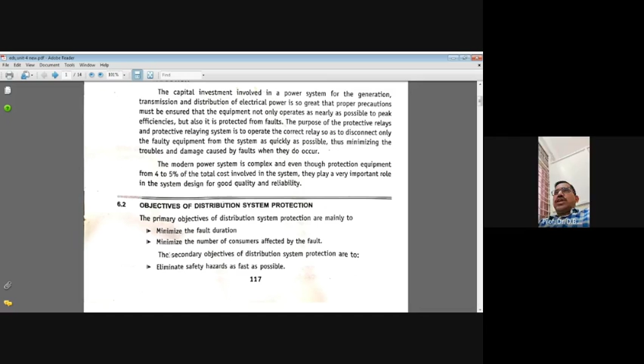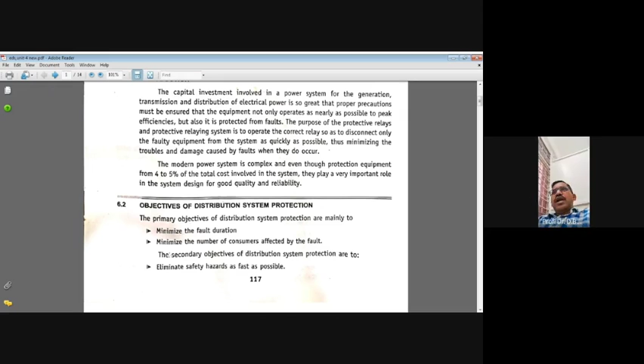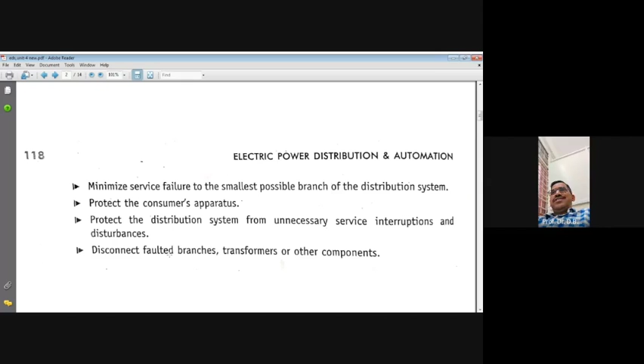The primary objectives of distribution system protection are: number one, minimize the fault duration, and minimize the number of consumers affected by the fault. The secondary objectives are: eliminate safety hazards as fast as possible, and minimize service failures to the smallest possible branch of the distribution system. Protect the consumer apparatus, and protect the distribution system from unnecessary service interruptions and disturbance. Disconnect faulted branches, transformers, and other components. These are the 7 objectives of distribution system protection.